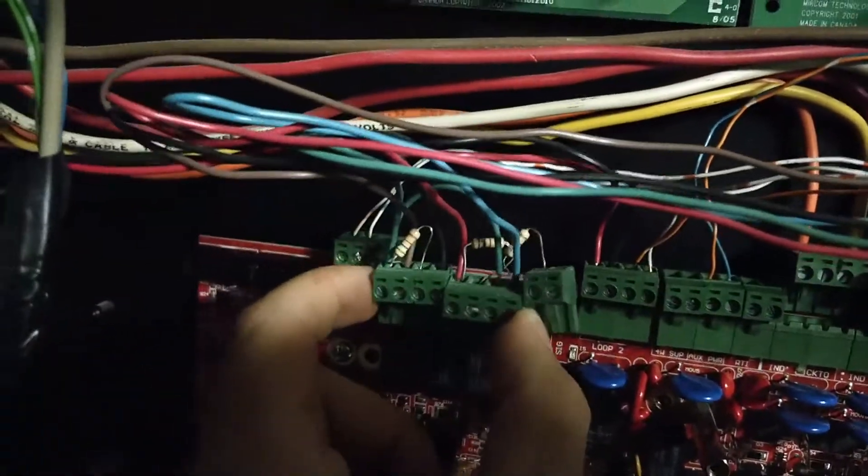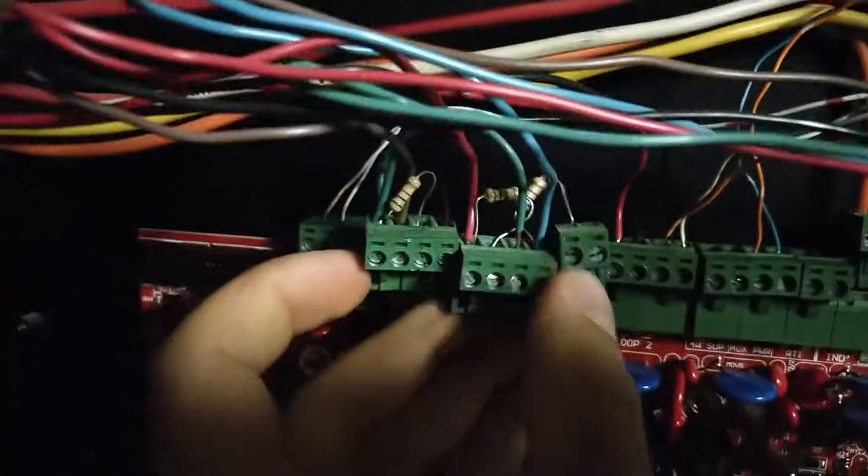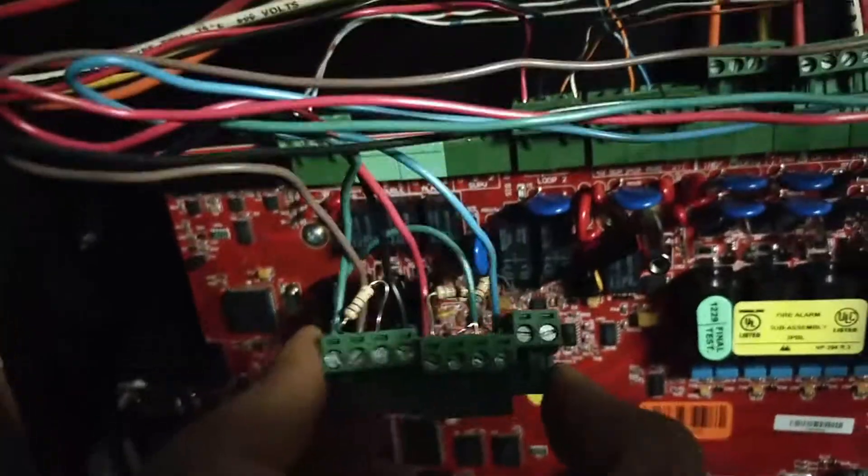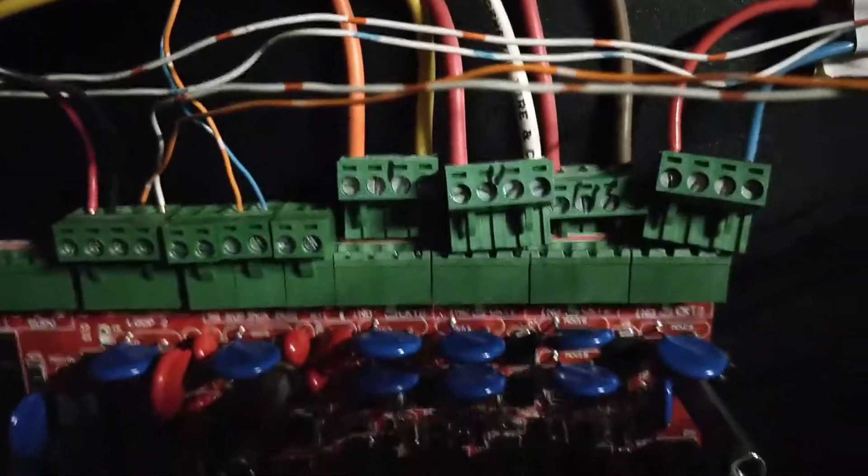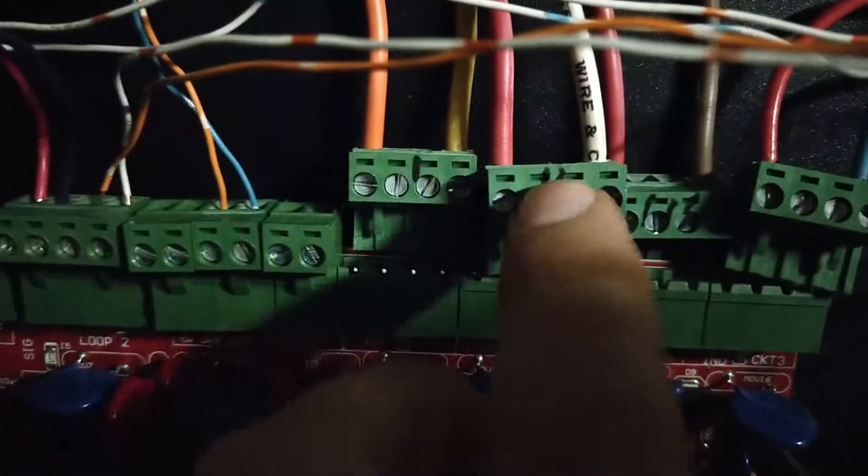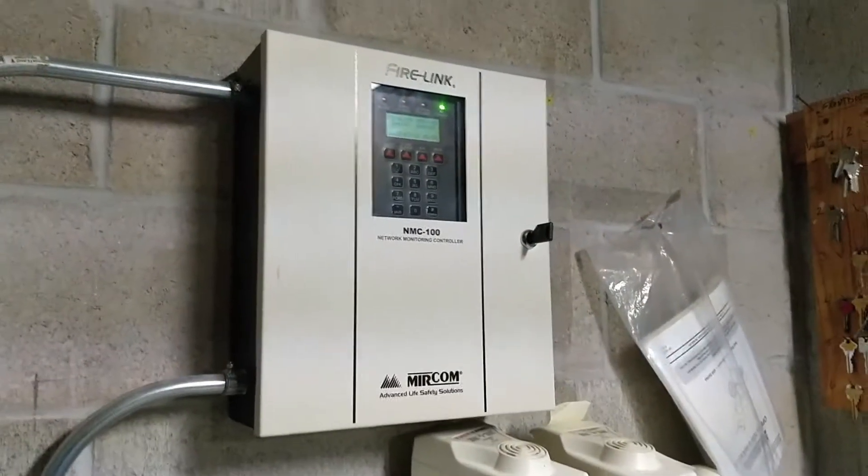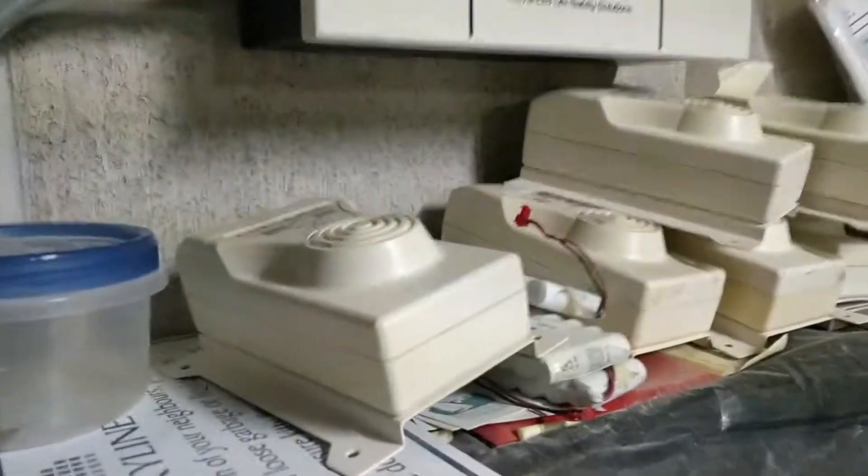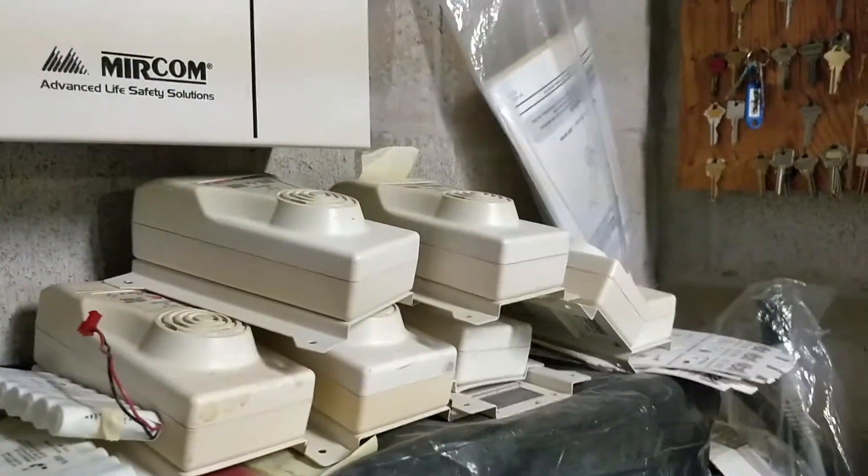So the only difference here is your alarm, supervisory, and trouble relays. They are a little bit different. You can still plug these in but I think I'm going to use the new ones anyway, because the way they oriented them in the new way compared to the older panel, it's a little bit better. So I'll just switch these ones out. You can see with the outputs, one easy way to keep track if you're going to do it this way - just put a little sharpie mark. One for one, two for two, three for three, and then the fire link. It was already labeled, so I knew that was in four. And there's again why I'm not shutting the fire link off, because that's the only connection to the main board. There's no programming or anything. It just sends the output to an input on there and then that lights up all these little horns in the apartments.